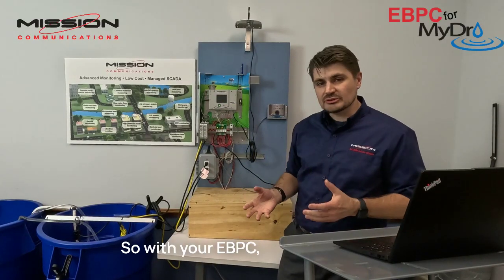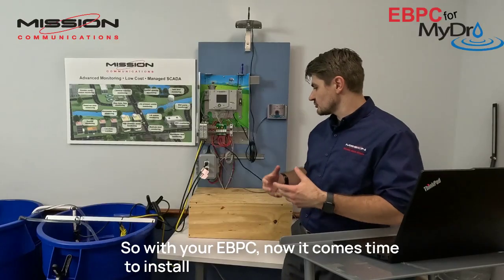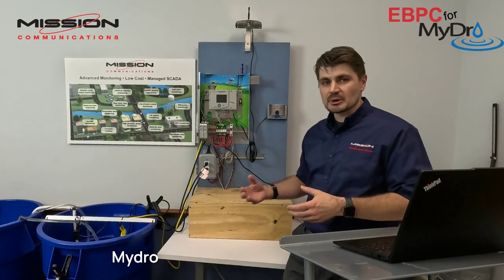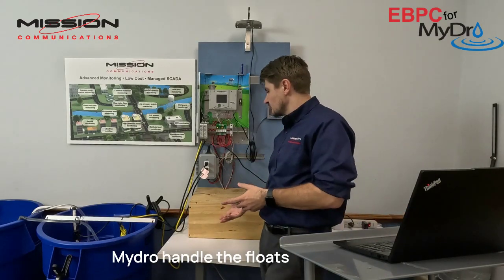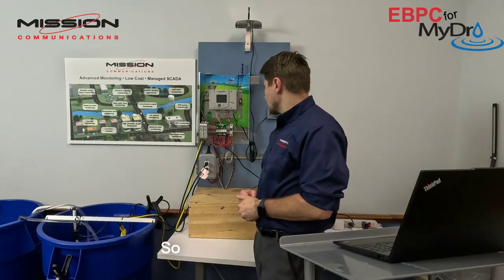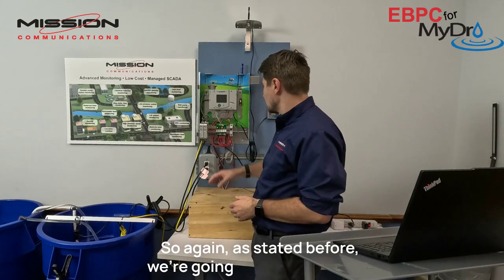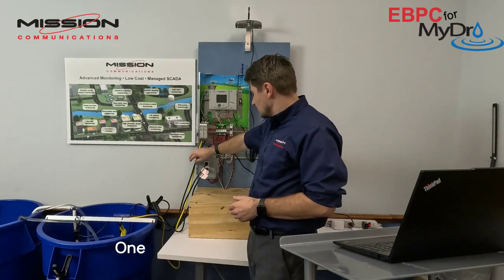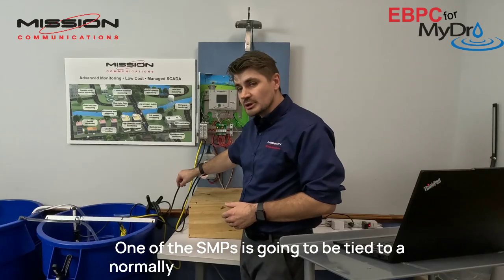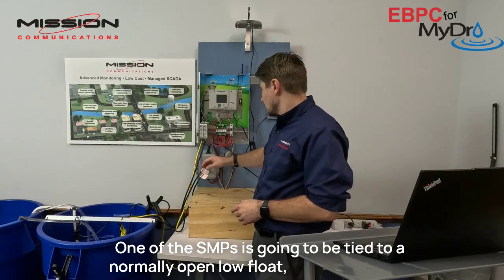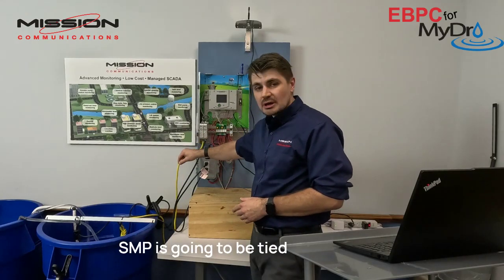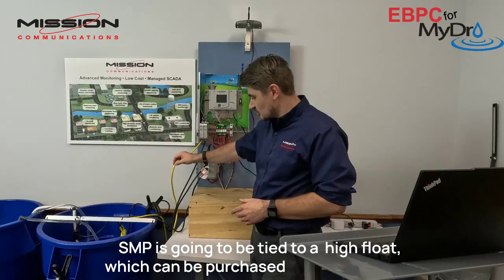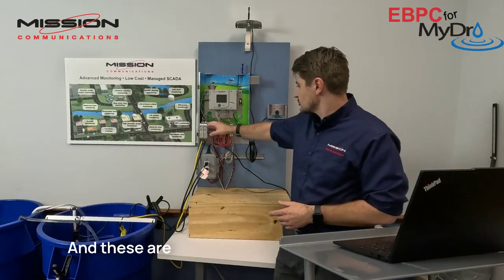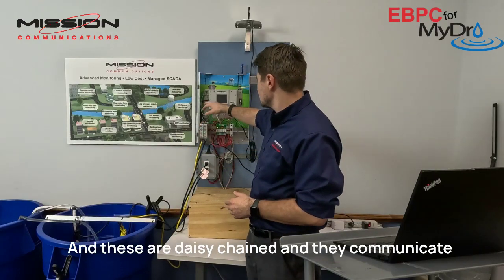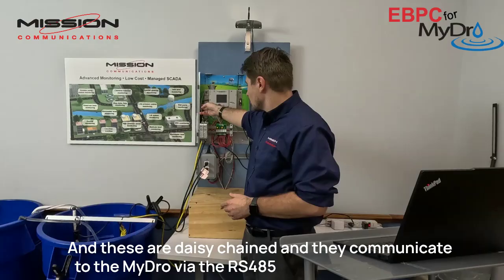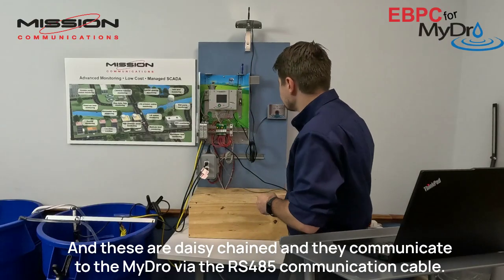So with your EBPC, now it comes time to install the equipment to help your MyDro handle the floats and the pumps. So again, as stated before, we're going to have 2 SMPs. One of the SMPs is going to be tied to a normally open low float, where the other SMP is going to be tied to a high float, which can be purchased through Mission. And these are daisy chained and they communicate to the MyDro via the RS-485 communication cable.